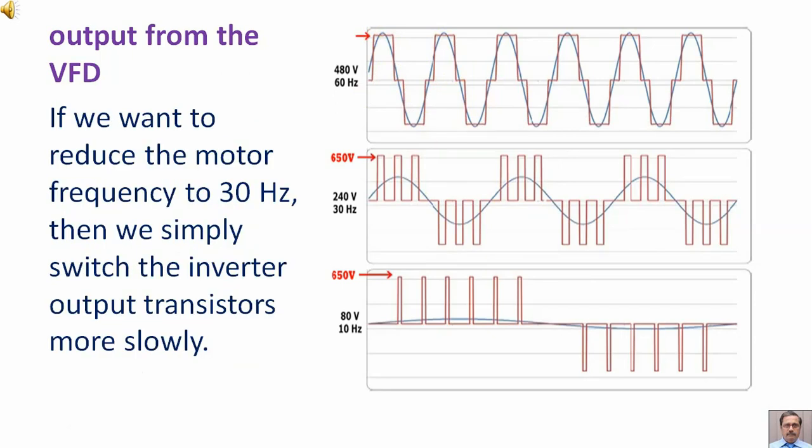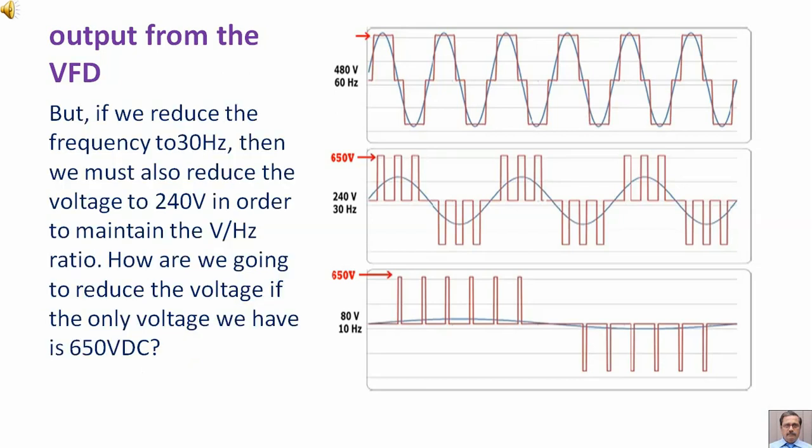If we want to reduce the motor frequency to 30 Hertz, then we simply switch the inverter output transistors more slowly. But if we reduce the frequency to 30 Hertz, then we must also reduce the voltage to 240 volts in order to maintain the voltage to hertz ratio. How are we going to reduce the voltage if the only voltage we have is 650 volts DC?